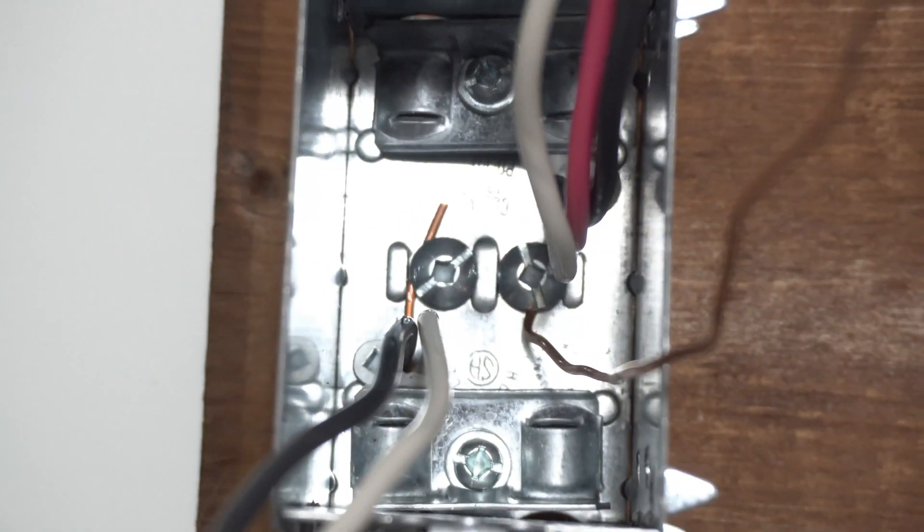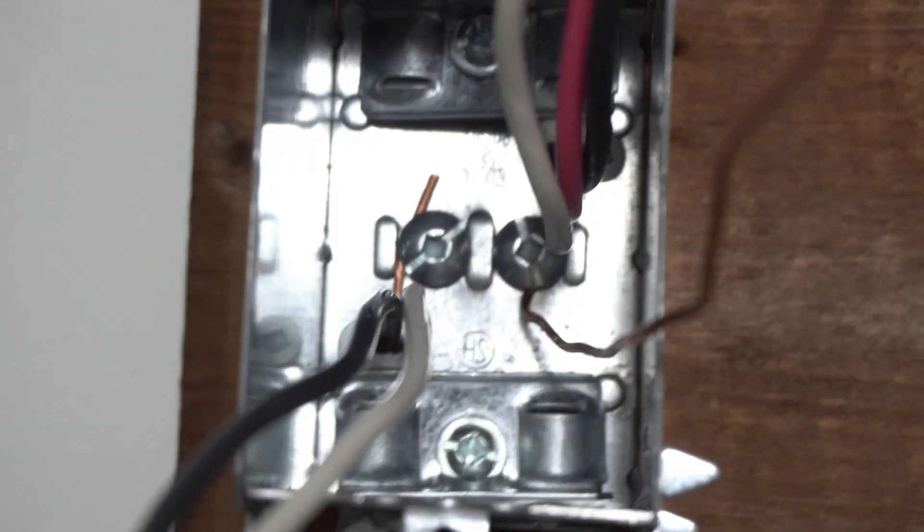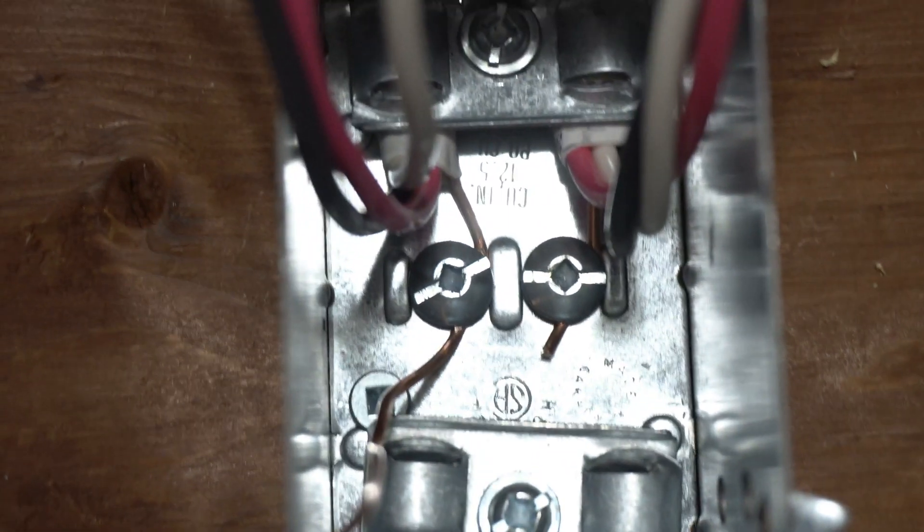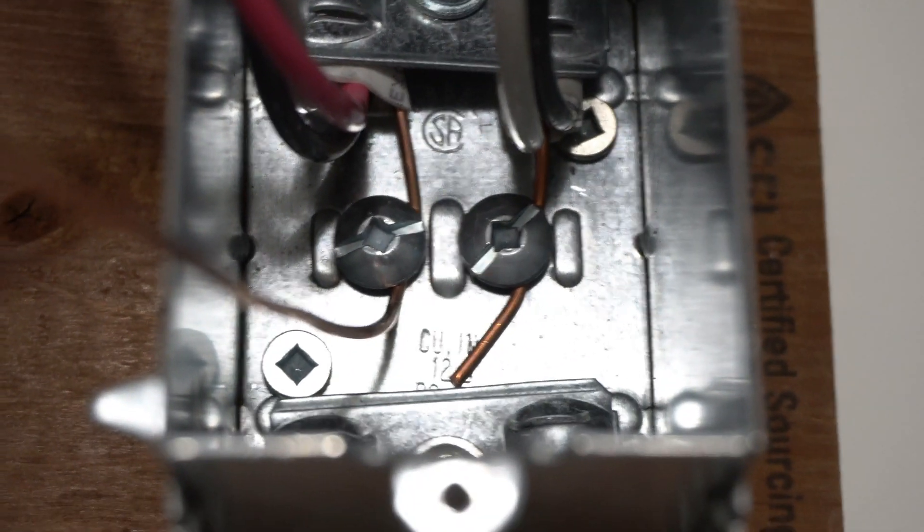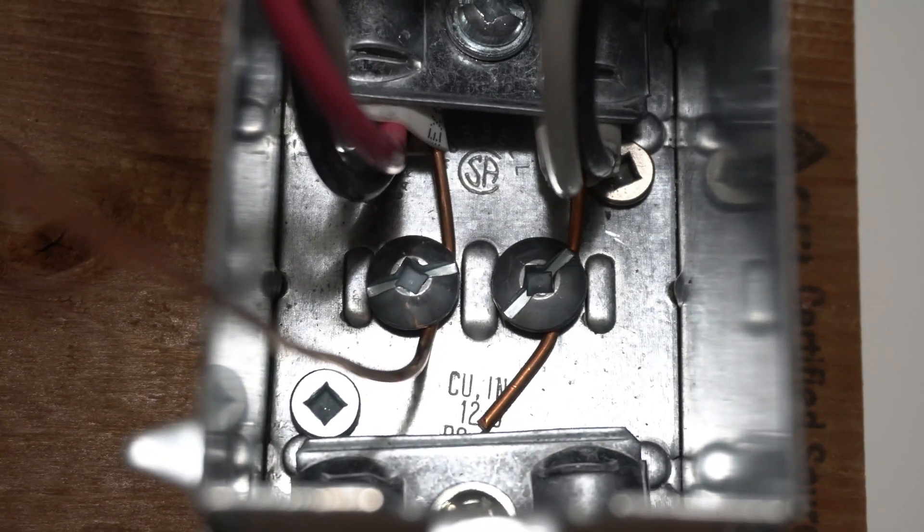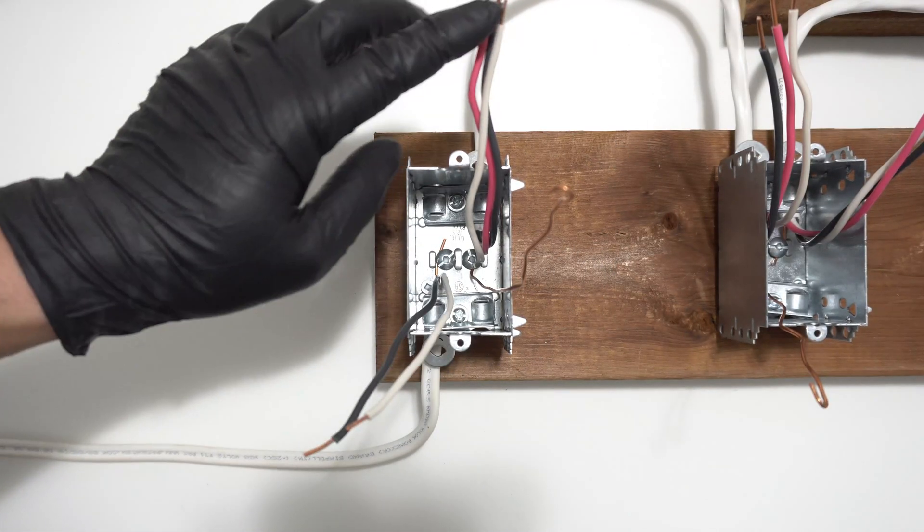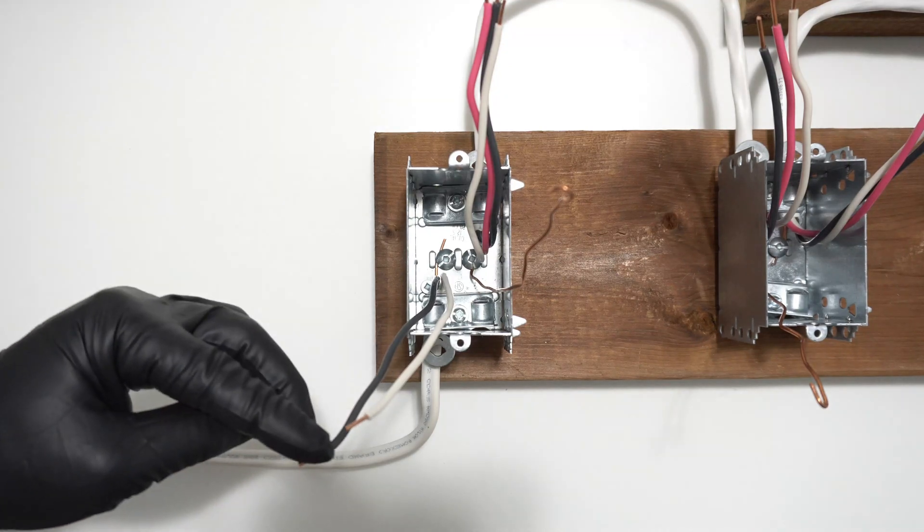Let's start with the ground wire. We must bond the box. One wire underneath each screw. One wire we will leave hanging about six inches long and the other one we can cut short nearby the screw. We will do the same to all the boxes. All the wires here, the ends are stripped down to one centimeter.